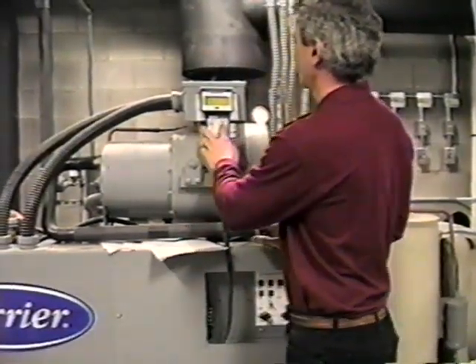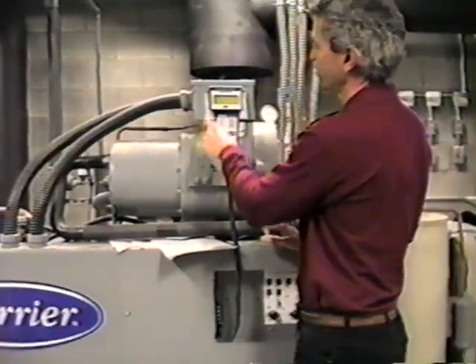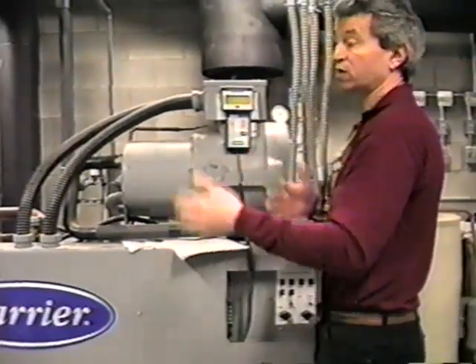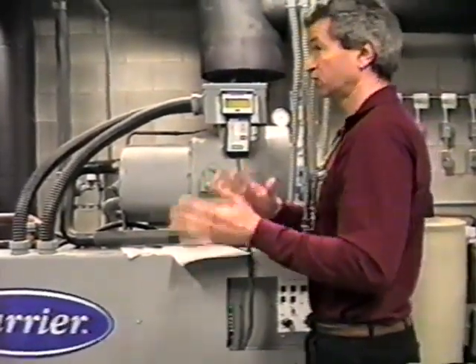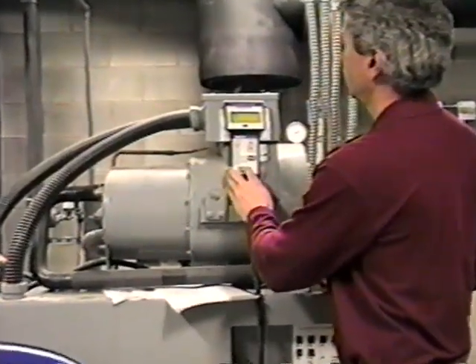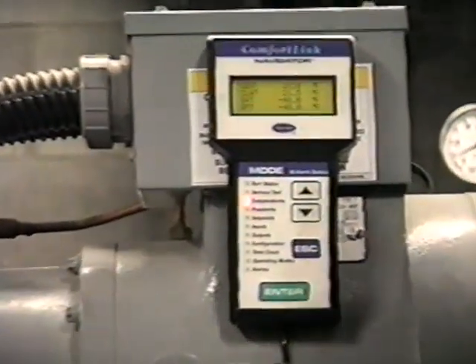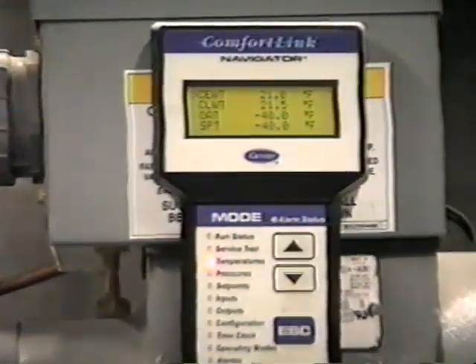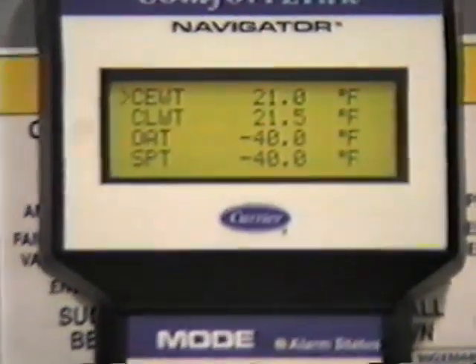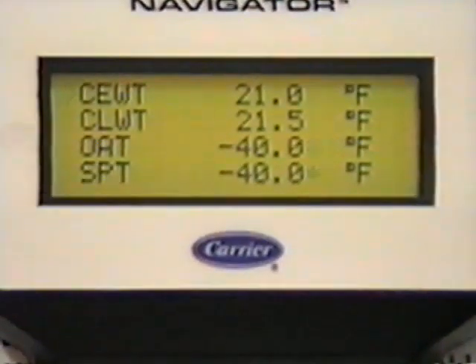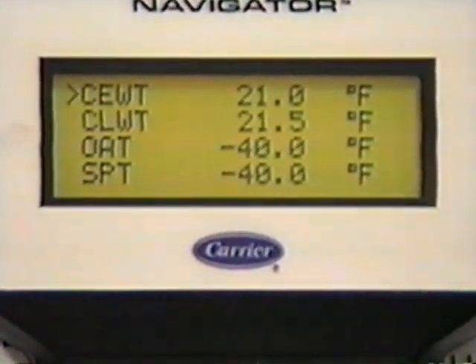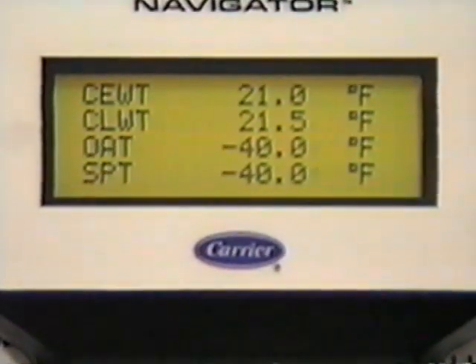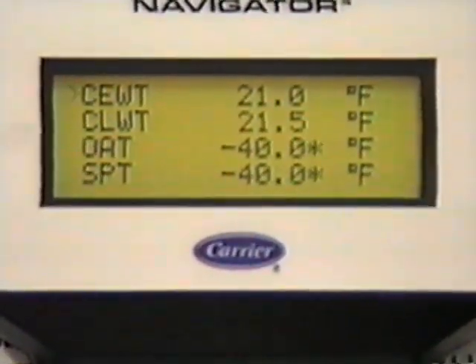Okay, so if we scroll back up, or if we can scroll down, you'll see unit. And again, remember, we're still in the temperature primary mode, so we're only going to be looking at temperatures. So if you hit enter on unit, you'll see the temperatures related to the whole machine, or both circuits. In this case, all we're looking at is CEWT and CLWT. So how do we expand that? If we wanted to expand that to find out what each one of those temperatures were, how did I say to do that? Press both at once.